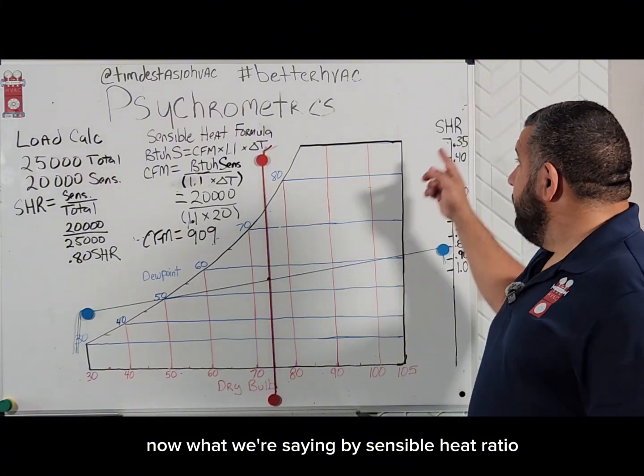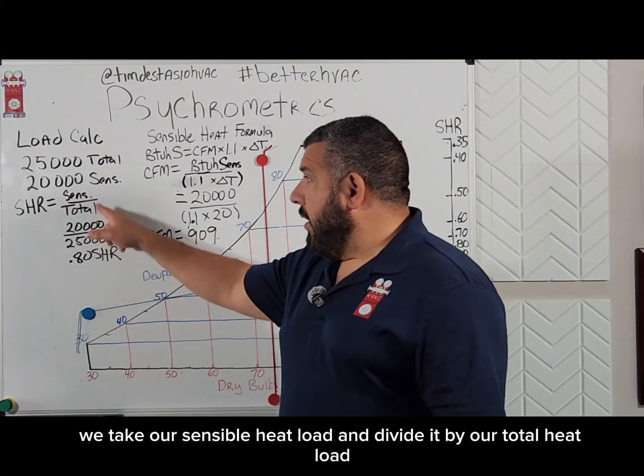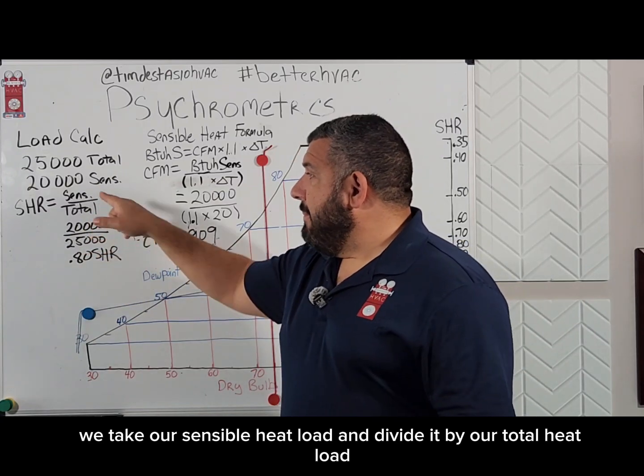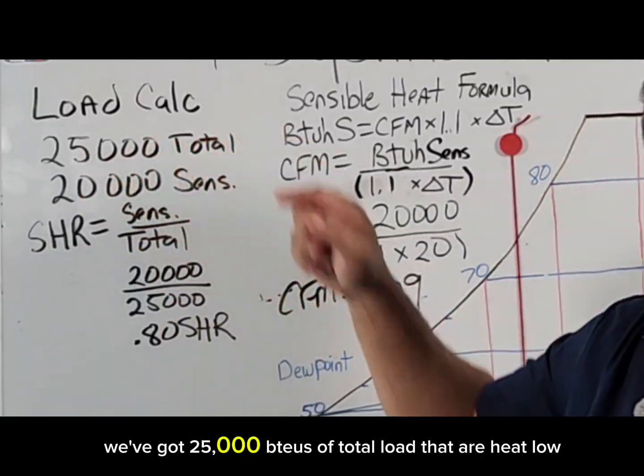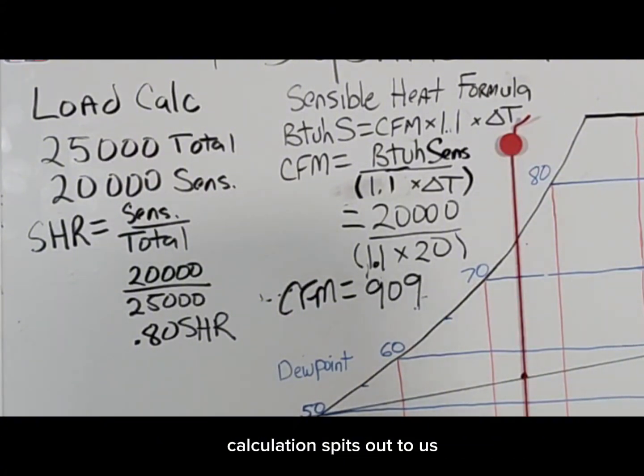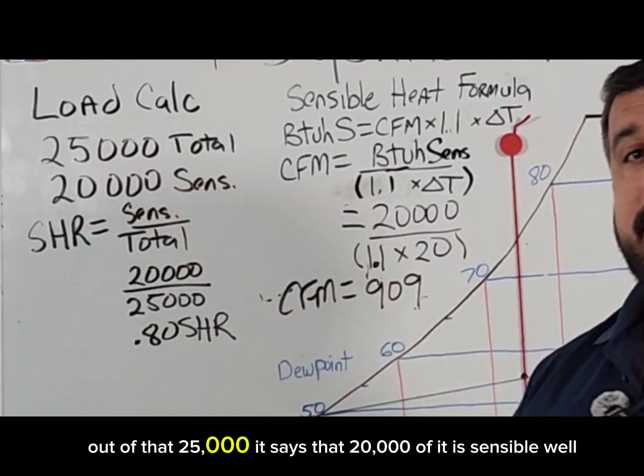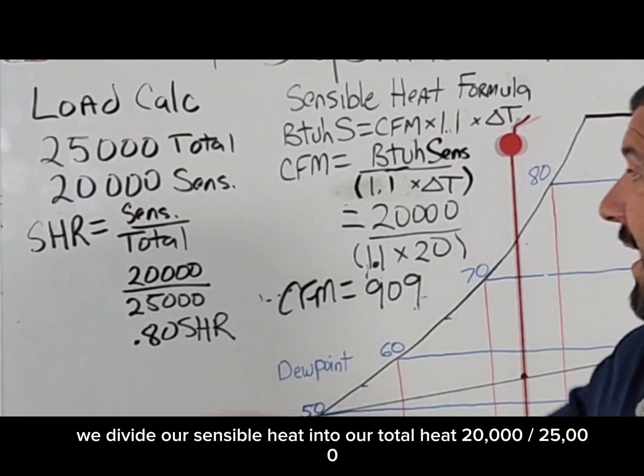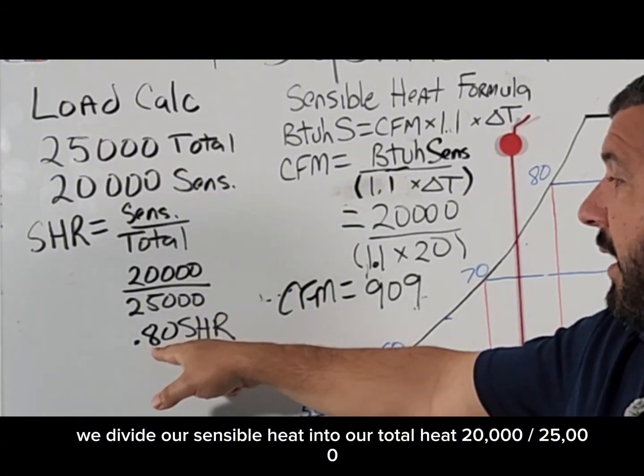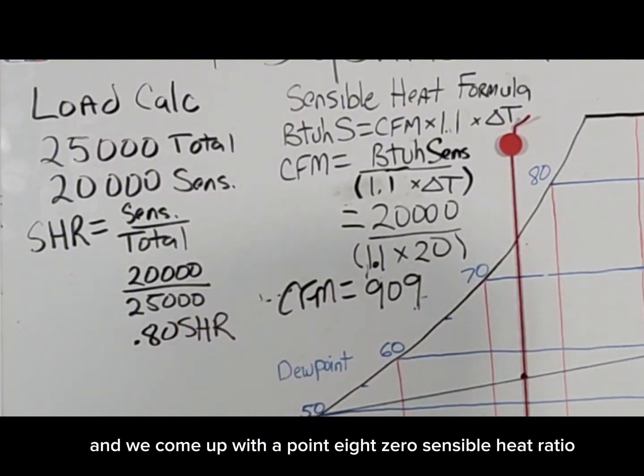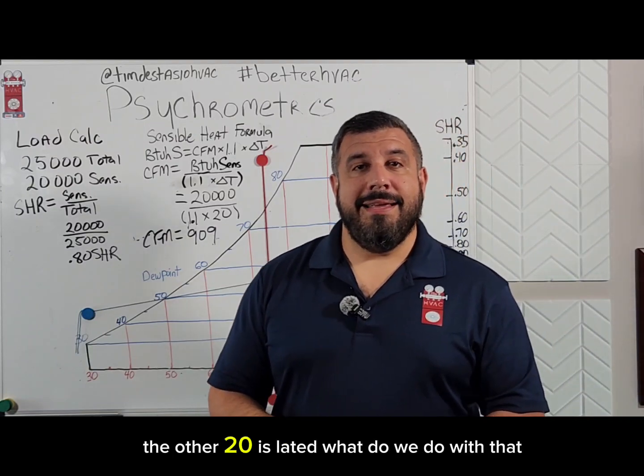What we mean by sensible heat ratio is a formula we use when we do a heat load calculation. We take our sensible heat load and divide it by our total heat load. For example, if we've got 25,000 BTUs of total load and 20,000 of it is sensible, we divide 20,000 by 25,000 and come up with a 0.80 sensible heat ratio — meaning 80% of that load is sensible and the other 20% is latent.